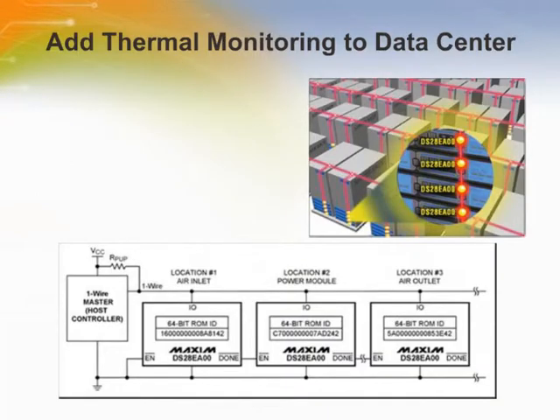Precise and adaptable thermal management is imperative for efficiently managing the energy consumption of data centers. The ambient temperature in a data center or other thermally controlled environment is not constant throughout the space. Temperature varies significantly across the vertical and horizontal planes, depending on proximity to active or inactive equipment, as well as airflow. The ability to identify specific areas where ambient temperature needs to be reduced is the key to reducing data center power consumption. Multiple temperature measurement nodes, combined with appropriate temperature data processing, enable an optimized environmental temperature control system that saves power and reduces costs.